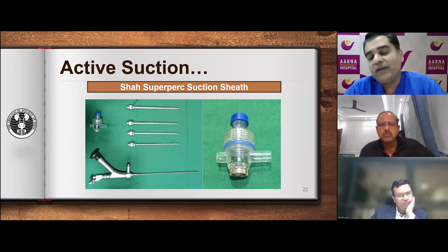And this is the setup. There are 4 sizes of the sheath: 12, 15, 18, and 21. And we can use our own mini nephroscope, which is 12 French. And this is the connector. On one side, there is a pinch valve mechanism wherein we can activate the suction. On the other side, there is a suction attachment. And this is the complete assembly.